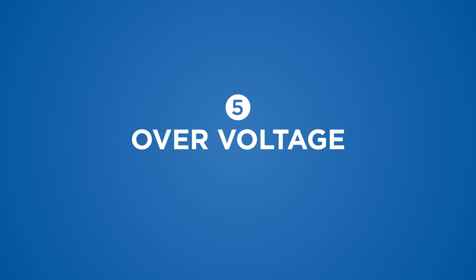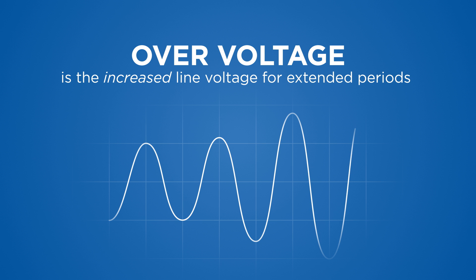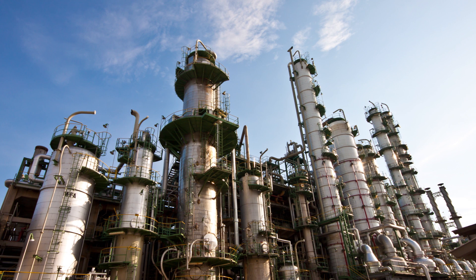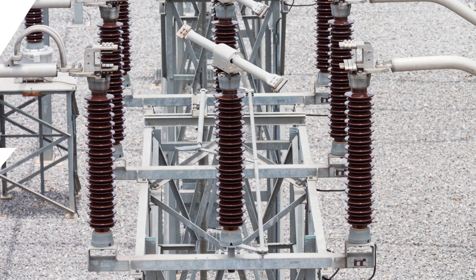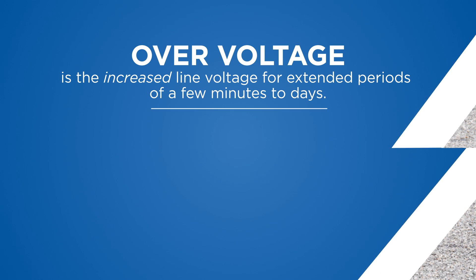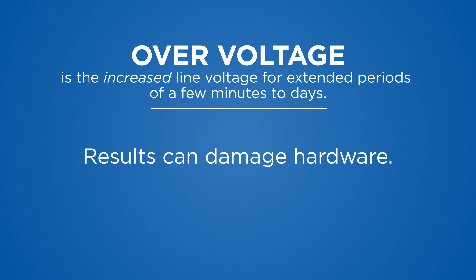Over voltage is increased line voltage for extended periods of a few minutes to a few days. It is triggered by a rapid reduction in power loads, heavy equipment being turned off, or by utility switching, and can potentially damage hardware. For protection against these five power problems, a single-phase line interactive UPS for more critical applications is the best solution.